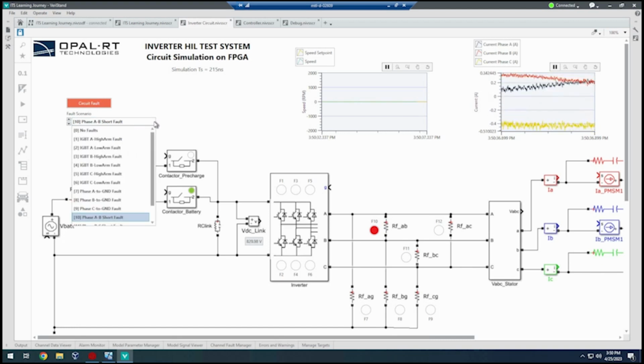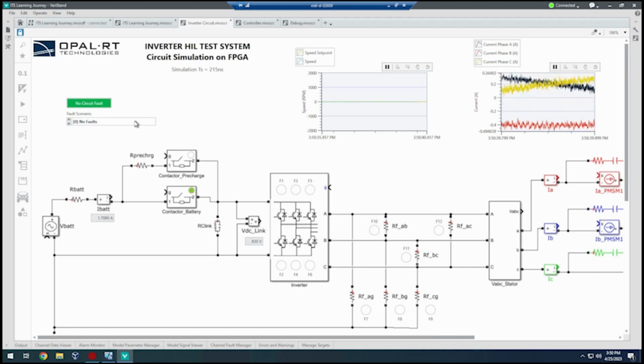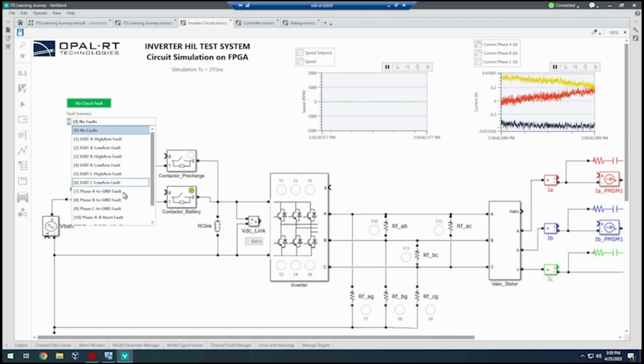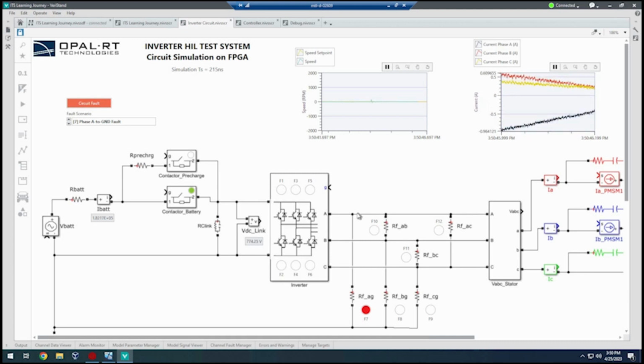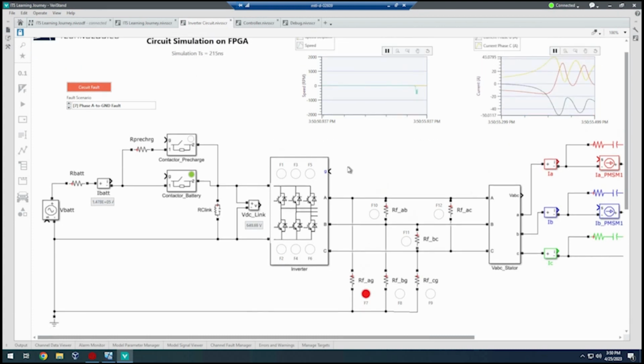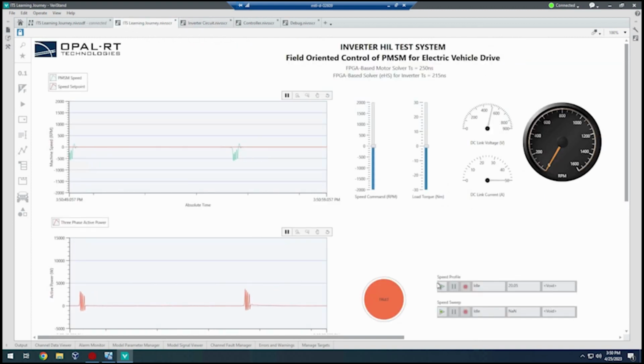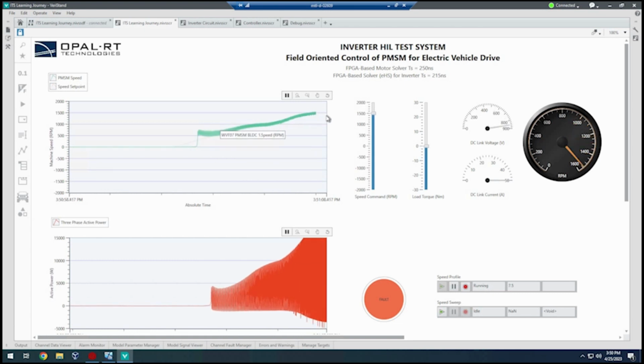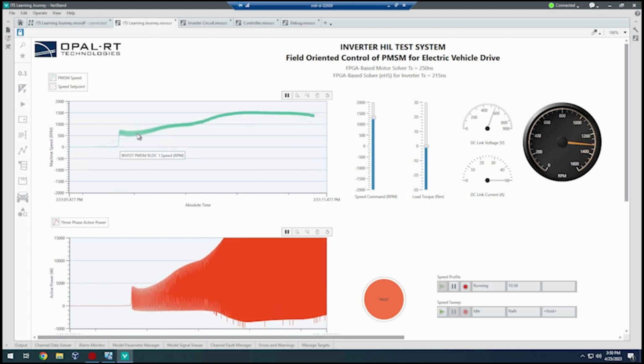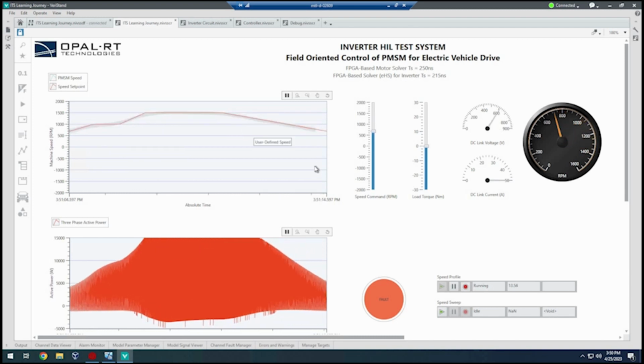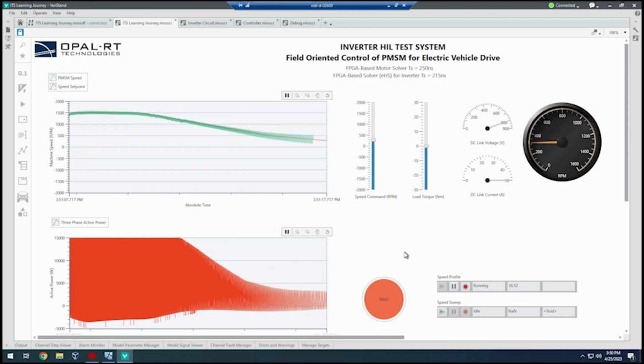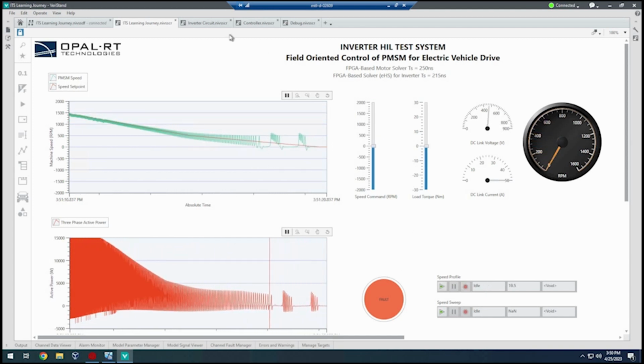I'll turn this fault off. We also have other faults. A different one would be something like a phase A to ground fault. Here is phase A, and the scenario says reduce the resistance to 1 milliohm and then tie it to ground. It's a similar situation to before, but you can see these speed blips as the machine tries hard to control the speed. In this case, the PI controller is probably overtuned, so it overcompensates for one of the legs being essentially tied to ground, and we see all this different current.